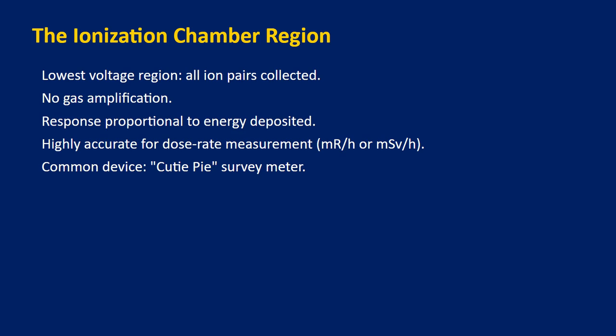The ionization chamber region. The first stop on our voltage curve is the ionization chamber region. At this relatively low voltage, we simply collect the electrons that the radiation knocked loose, nothing more, nothing less. Because the electrical signal is directly proportional to the total energy the radiation left behind, these meters are incredibly accurate at telling us the dose rate.